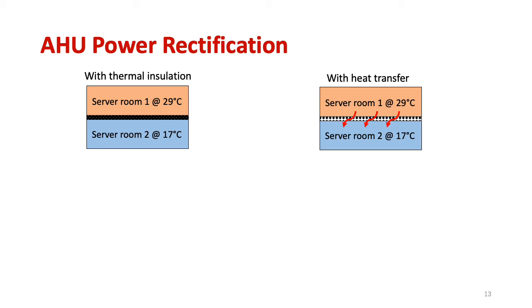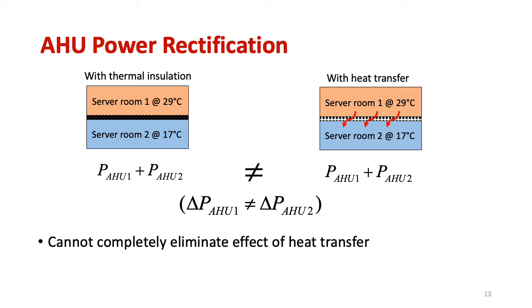Now we consider the problem of how to rectify the AHU power readings to address the heat transfers. We use a two-room example to illustrate the challenges. Because the power consumption of the AHU is nonlinear to the amount of heat removed, the total powers of the two rooms in the presence and the absence of the thermal insulation are different. Specifically, the changes of the two rooms' HU powers due to the heat transfer are different. Therefore, we cannot completely eliminate the effect of the heat transfer.